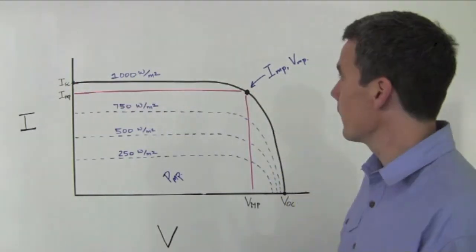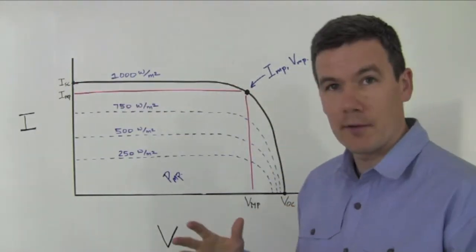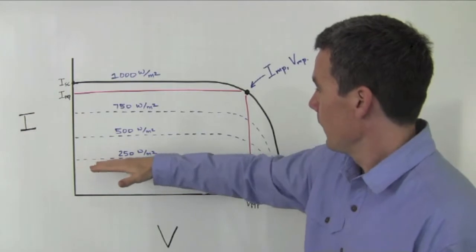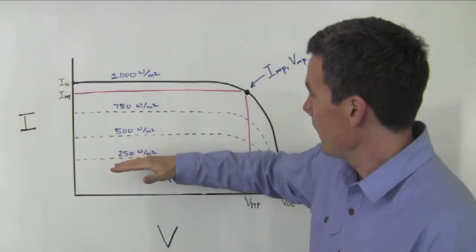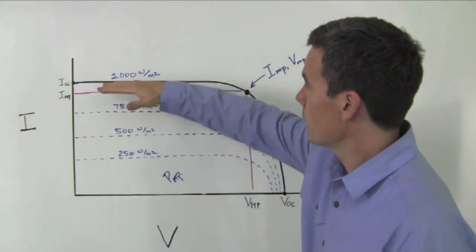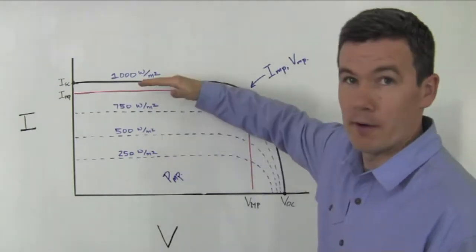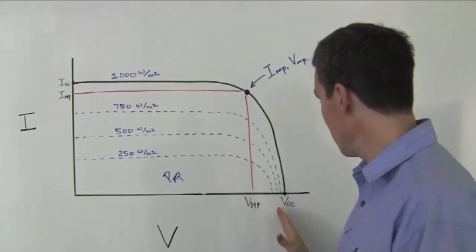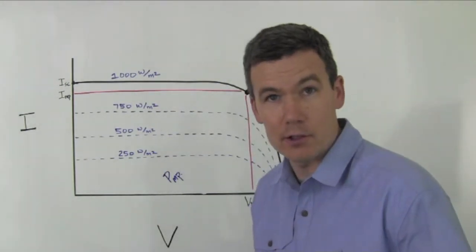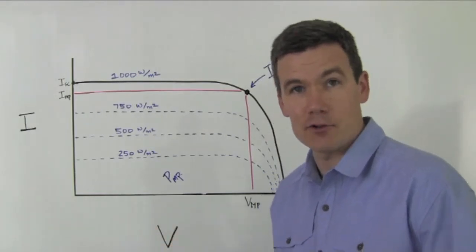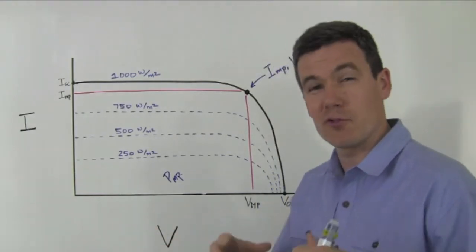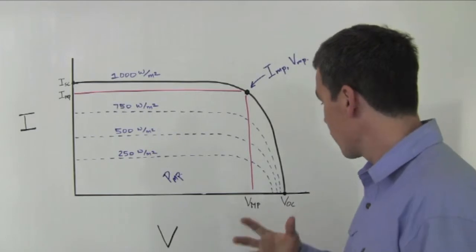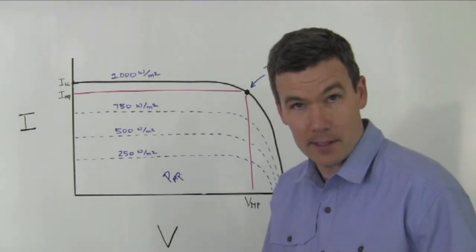Now this current varies with the voltage throughout the day. We start at lower irradiance through the day and as irradiance builds, this curve gets taller. It doesn't necessarily change the open circuit voltage as the irradiance changes. The open circuit voltage is relatively constant throughout the day no matter what the irradiance is.